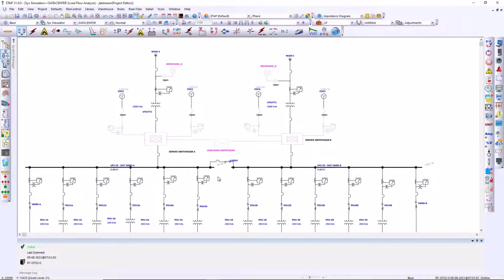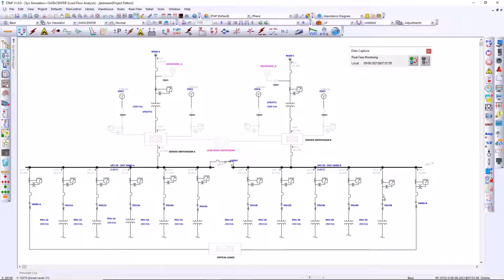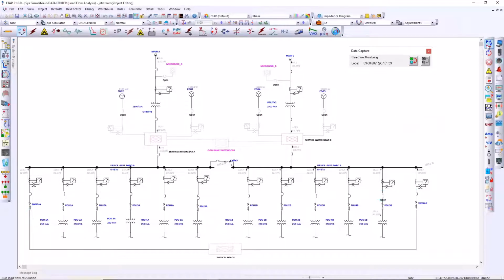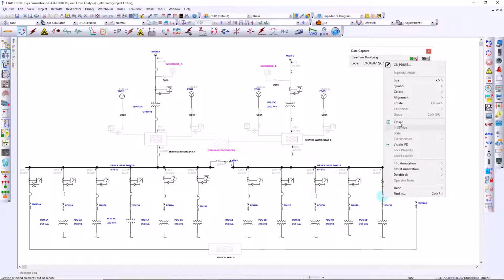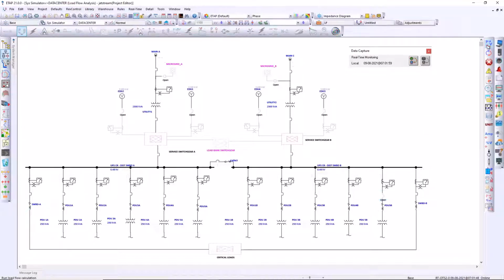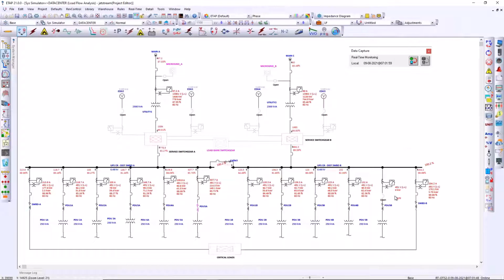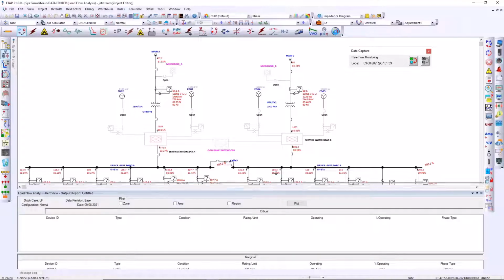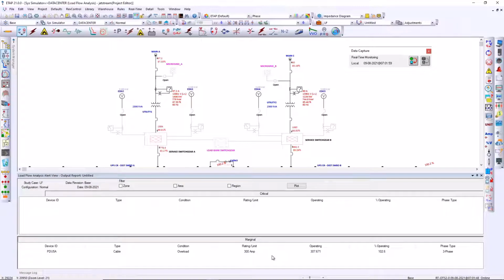In this case, we can start using ETAP's predictive analysis modules. So for example, I want to evaluate the effect of opening this circuit breaker, get online data, and then simulate it being open, then run load flow. Now you can see all the flow through this circuit breaker is 0, where on the other side I have an alert condition. I can see from my load flow alerts that I have a capacity alert for that cable.